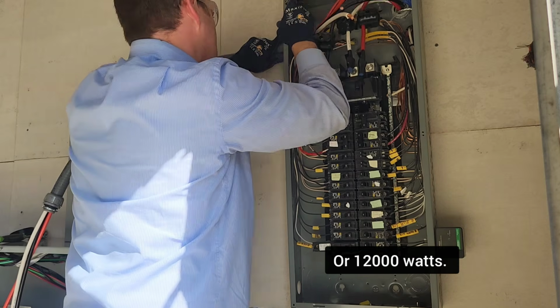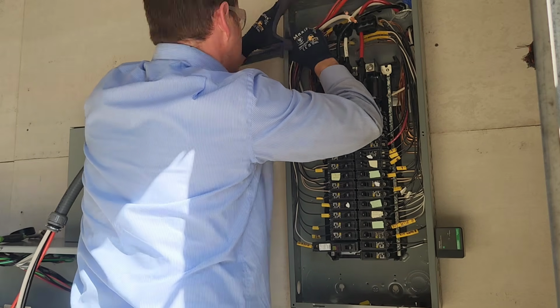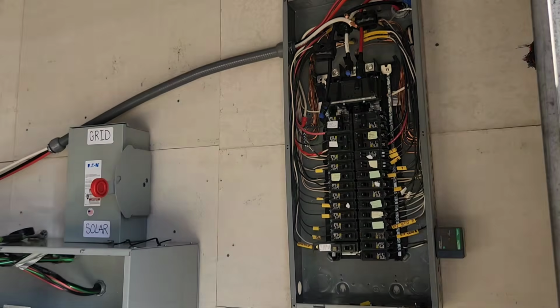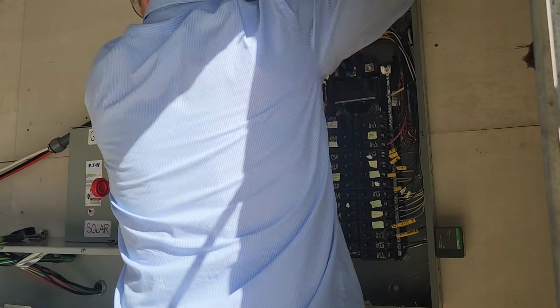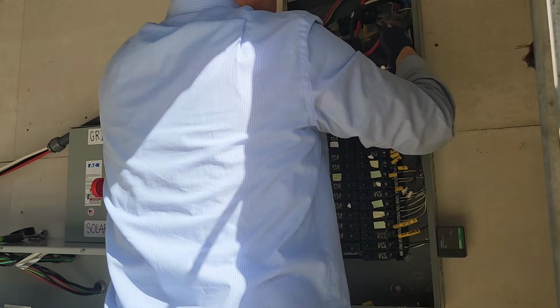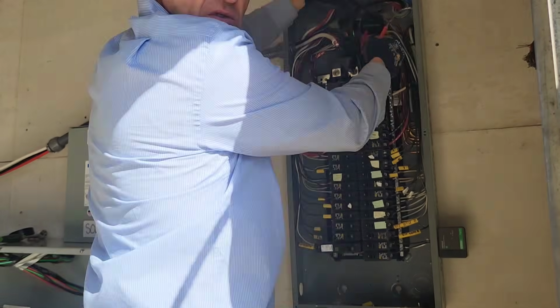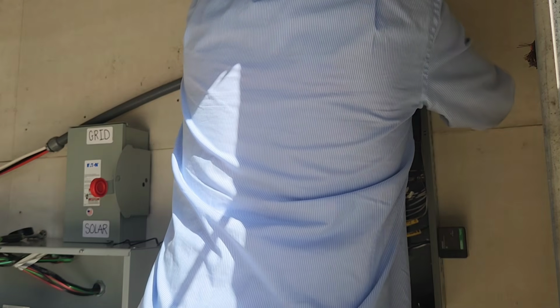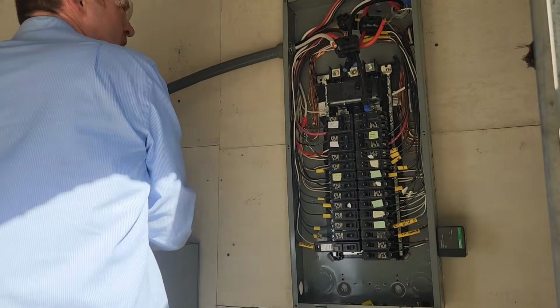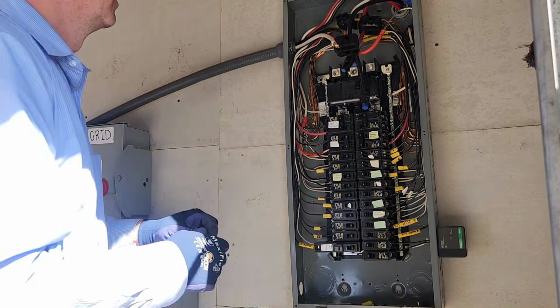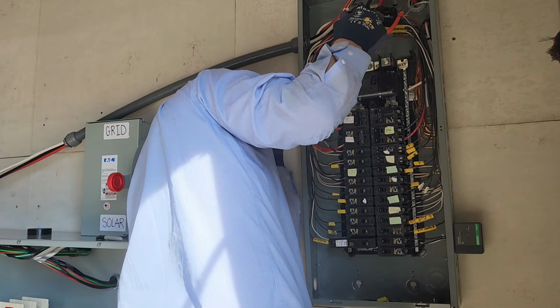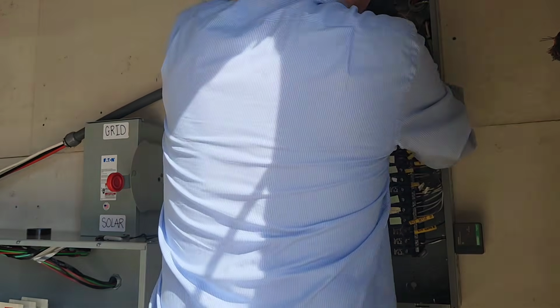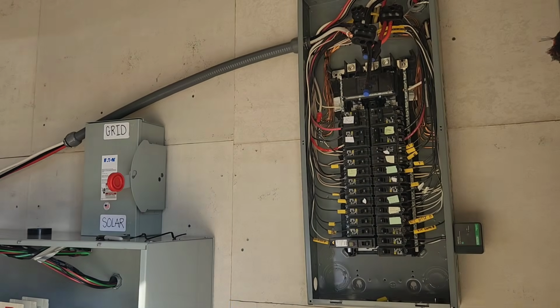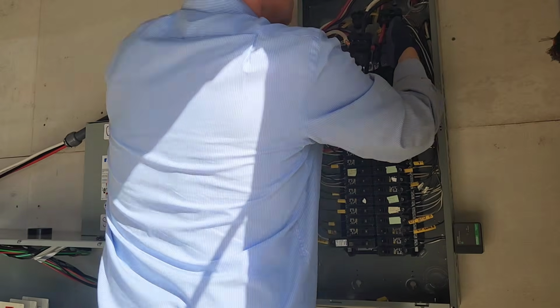So even if you have 200 amp service at your house—a lot of people do, especially with newer houses—you're probably not even coming close to using 200 amps. If you do have 200 amp service, it'll be a lot more difficult to install this because you're working with much thicker wire. If you can convert your service down to 100 amps, that would make it a lot easier, since this 2 gauge wire, even though it's only 2 gauge, is fairly difficult to work with—a lot more than I thought.